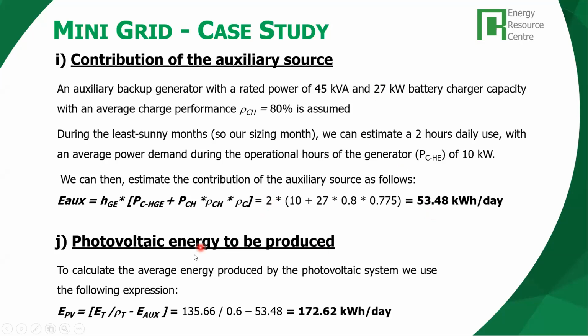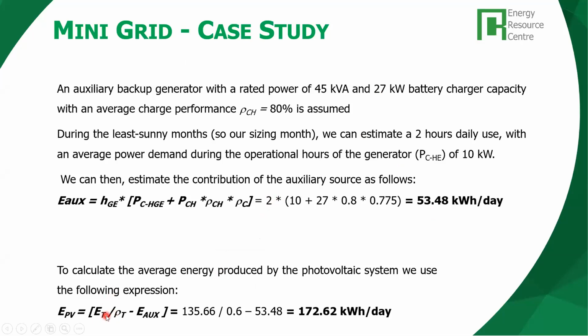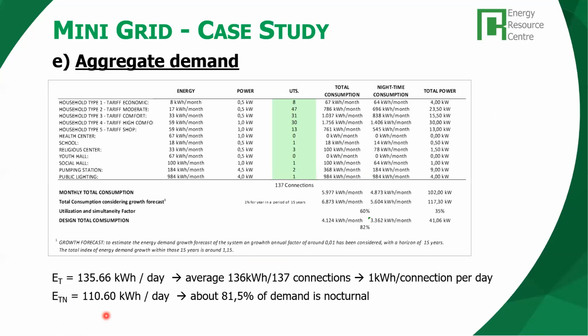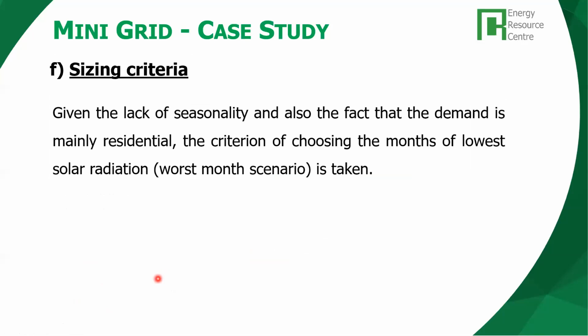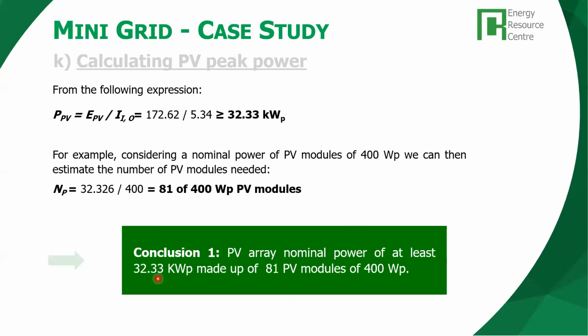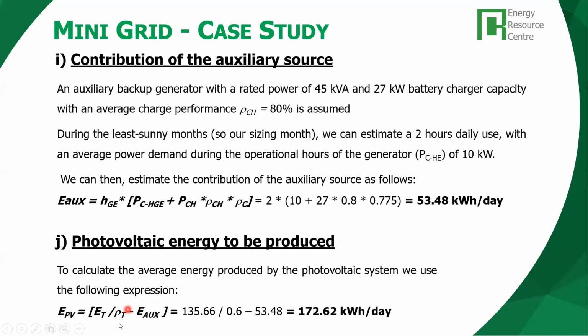So how much electricity do we need to generate with the PV panels finally? So we take the total energy demand. If you remember, the total energy demand from our table is 136 kilowatt hour per day, okay? We divide by the performance ratio, which was 60%, the total gross demand, total net demand, and we deduct the energy that will come from the diesel generator. So the result is 172.6, almost 173 kilowatt hour per day. That is what we need to generate with the PV panels.